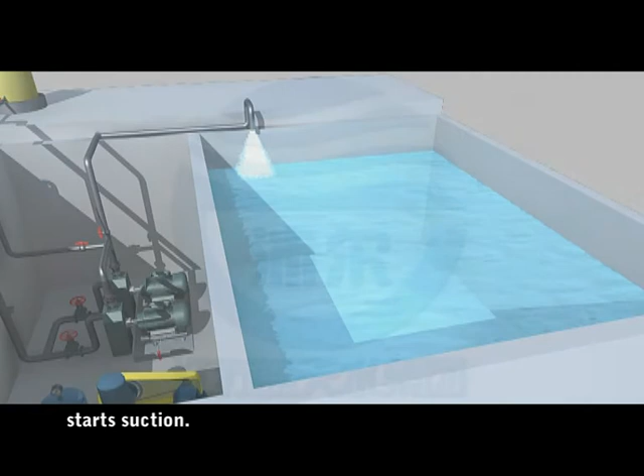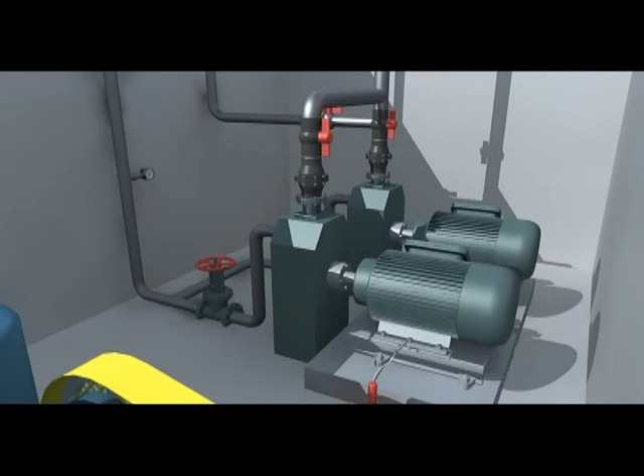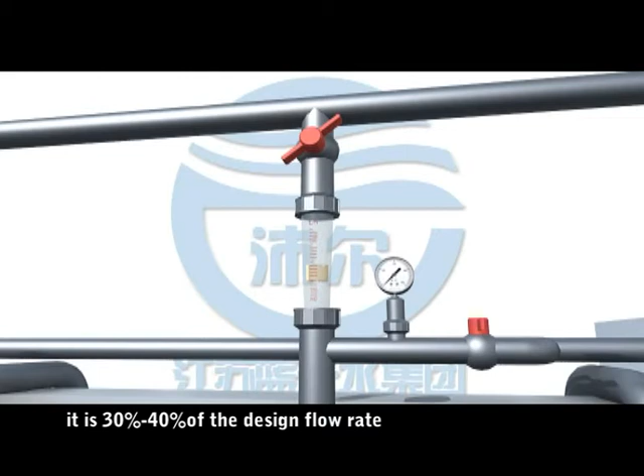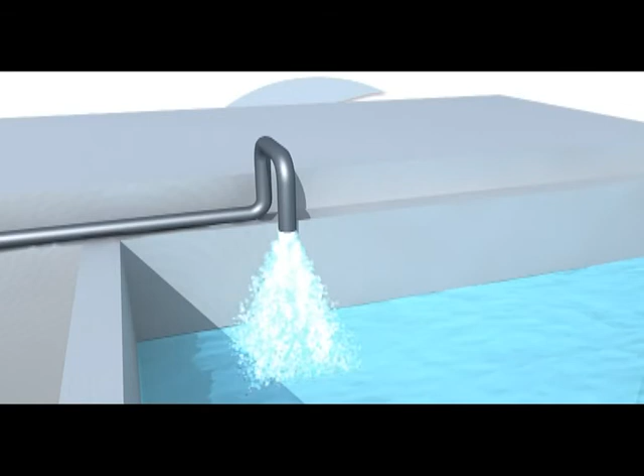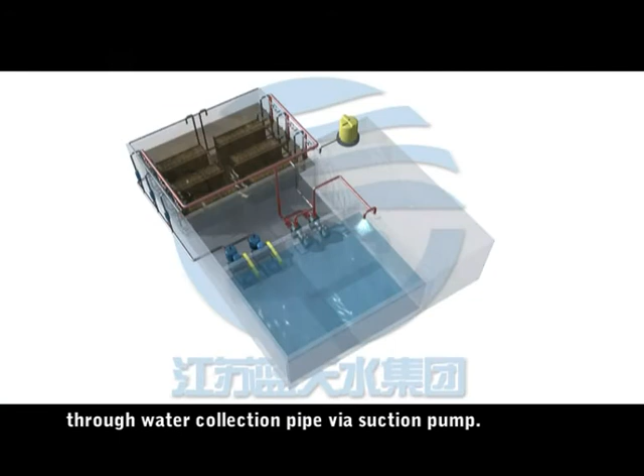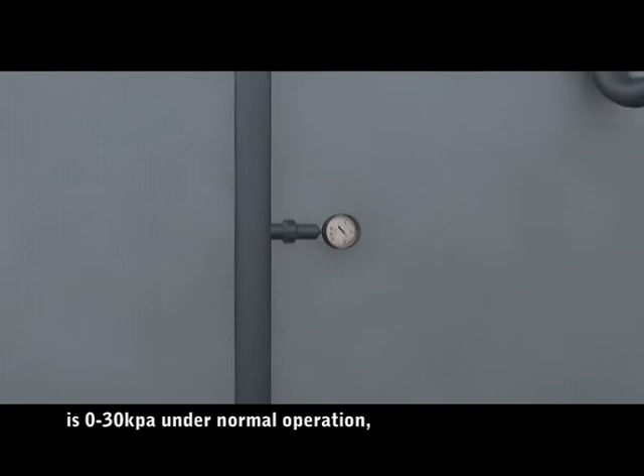2. Operation of membrane. When the system is under normal operation, open the self-priming pump. It is 30% to 40% of the design flow rate for the first 2 days. Keep suction, increase to design flow rate slowly, then keep normal suction. Treated water is pulled to the clean water tank through the water collection pipe via suction pump. Suction negative pressure is 0 to 30 kPa under normal operation.